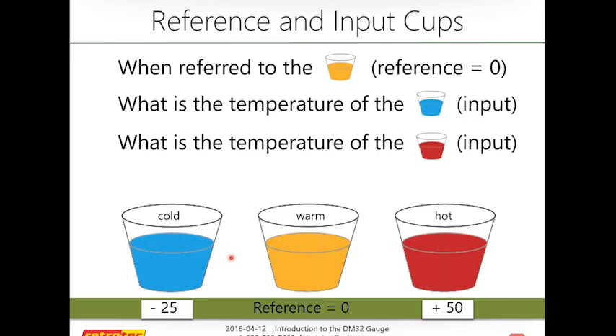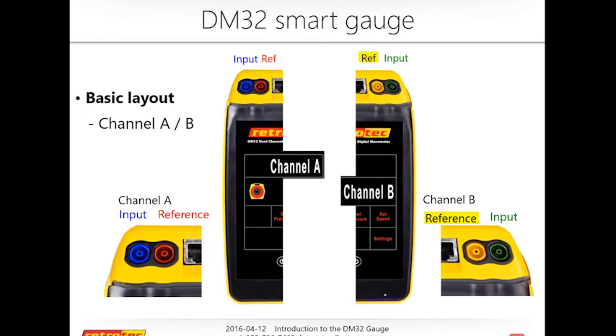And I want to talk, now that we've talked about what those manometers are and how they work, I can go back to explaining how those channels work. So again, keep in mind that when we talk about a channel, we're literally talking about separate manometers. So with the DM32 Smart Gauge, this is what the channel A input looks like, and the reference, so again, this is always going to be 0. And that is going to be read out on the top of the screen. And then channel B also has the input on the outside of the gauge and the reference on the inside of the gauge, and that will be found just underneath channel A.